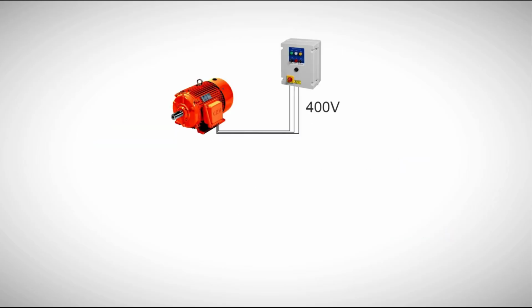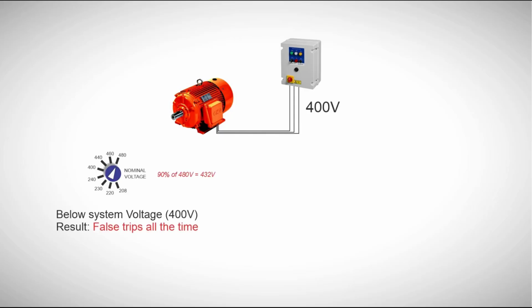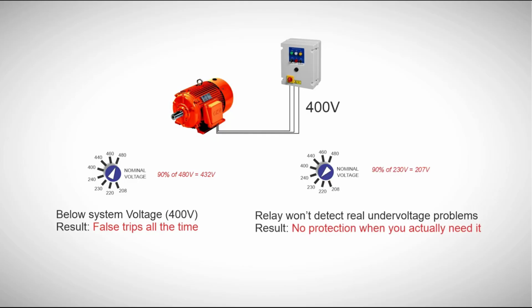Now, here's what happens if you set the nominal voltage incorrectly. If you set it too high, let's say 480 volts while your system is actually running at 400 volts, the relay will think your voltage is always too low. So even when everything is normal, it will keep tripping again and again. On the other hand, if you set it too low, like 230 volts, the relay becomes less sensitive. It won't recognize real undervoltage conditions, and your equipment could be running under unsafe conditions without any protection. So whether it's too high or too low, a wrong setting either causes constant nuisance trips, or worse, no protection at all when you actually need it.